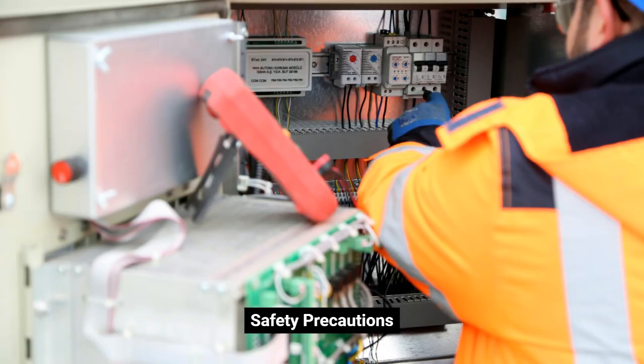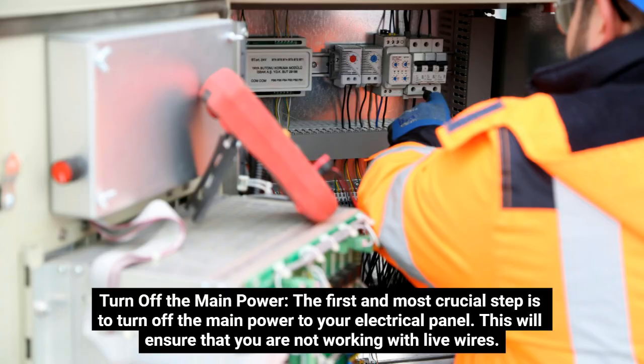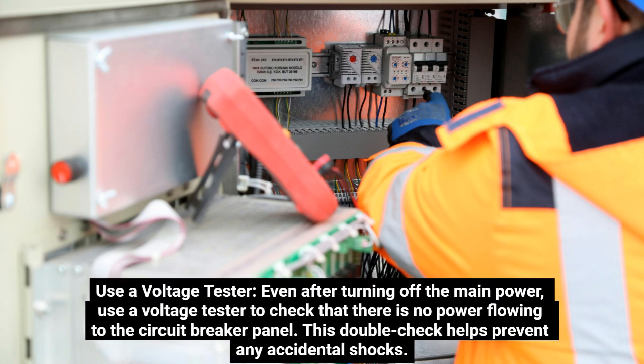Safety precautions. Turn off the main power. The first and most crucial step is to turn off the main power to your electrical panel. This will ensure that you are not working with live wires. Use a voltage tester. Even after turning off the main power, use a voltage tester to check that there is no power flowing to the circuit breaker panel. This double check helps prevent any accidental shocks.